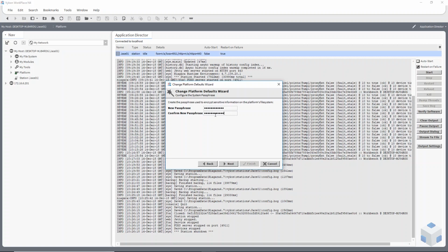So you have to enter a passphrase. It has to be 10 characters long, and I believe it needs to have at least one capital, at least one numeric value. And now the platform password I need to change. I'll just call this Tridium 1. Check that your password matches. Okay, it's telling me a summary there of what's going to happen. It's going to be removing the default Tridium account, and adding my new one here. Click finish. So that's before I even get to the commissioning wizard. I think it was N4.6 that changed this. This bit's been added. It used to be part of the commissioning wizard before.